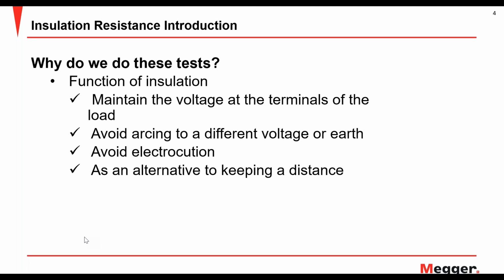So insulation resistance, why do we do these tests? The main function is to check the integrity of the insulation: when you supply the voltage, is it able to hold the voltage without losing or leaking to ground, avoid arcing at different voltages or leaking to earth, and obviously protect personnel from electrocution or shocks. As an alternative to keeping a distance, you have insulation to protect any personnel that is there.